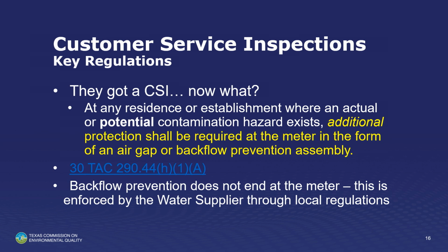But also something I'd like to mention here, a lot of times on things, I was talking about restaurants, we do a lot of internal protection too. It's not just at the meter, but we do a lot of stuff out there. Maybe they've got filters or whatever. We're protecting those ice machines. We're protecting those carbonators. We're protecting the coffee machines, all this stuff out there. It's not just at the meter. And they may have one at the meter. They can have an RP or be protected at the meter. But we want to protect those people inside that building as well. We want to protect them.